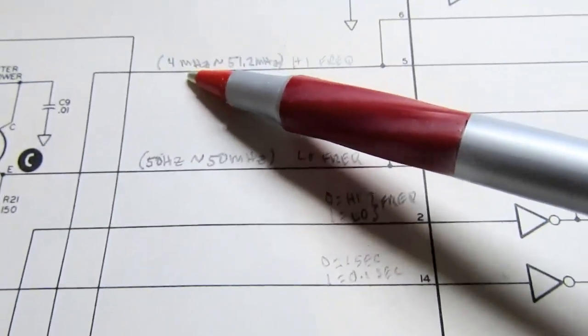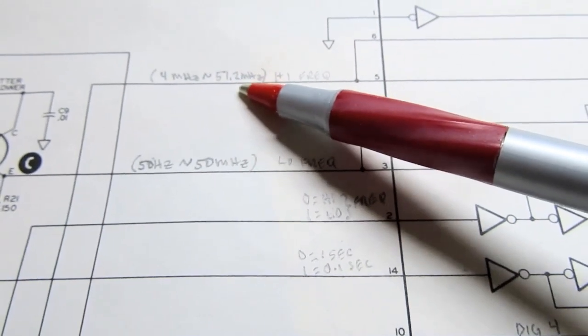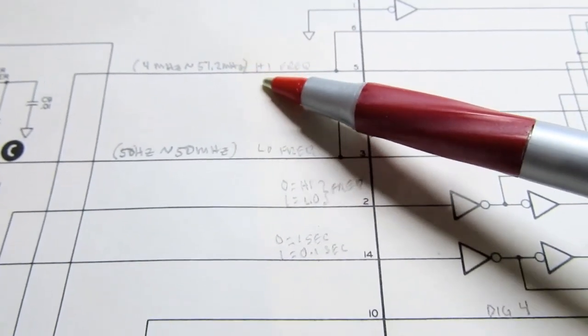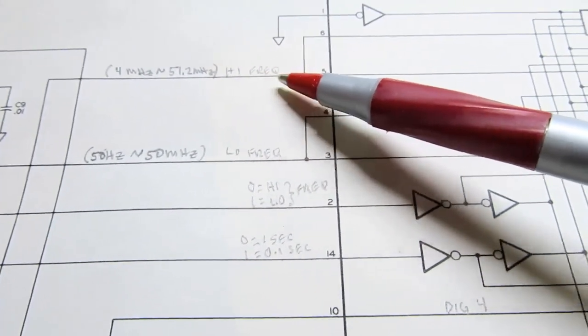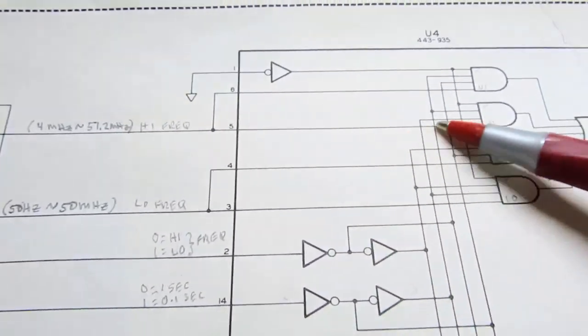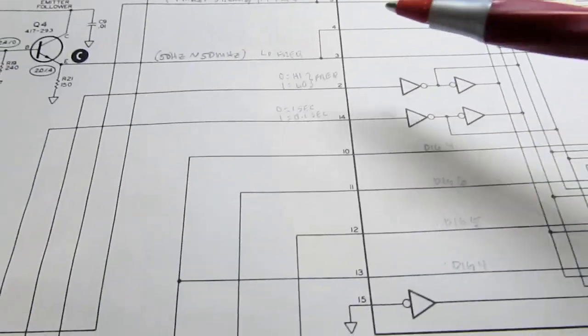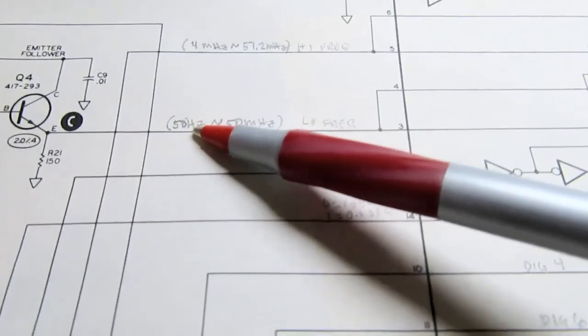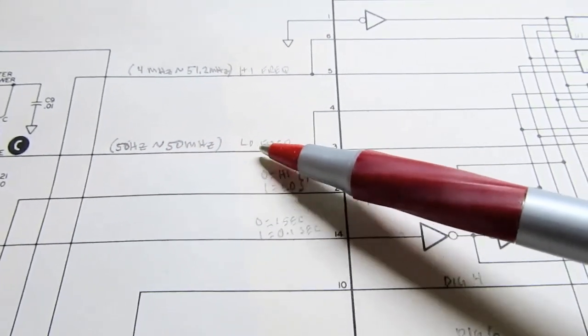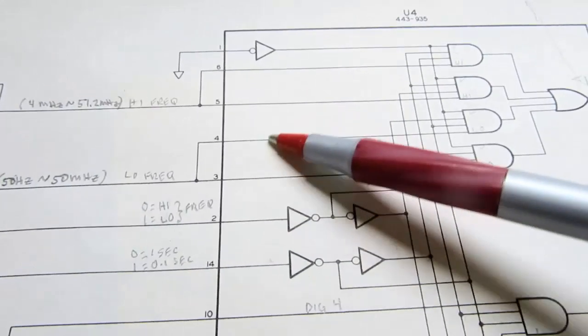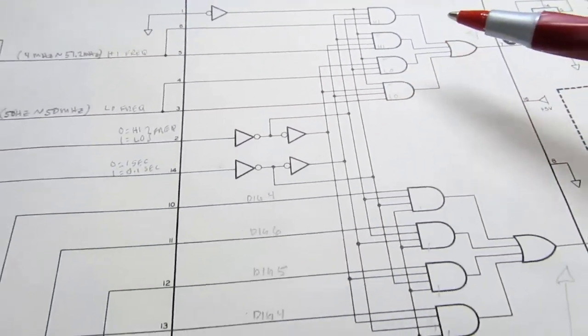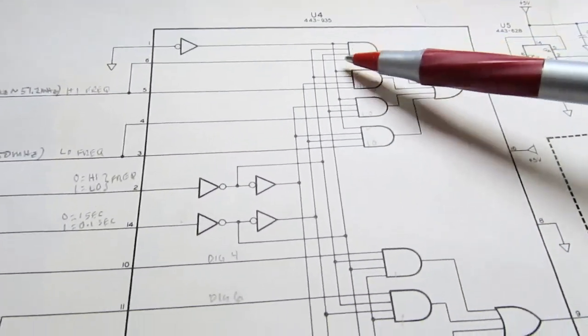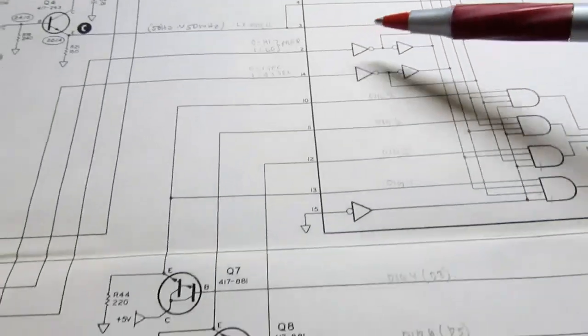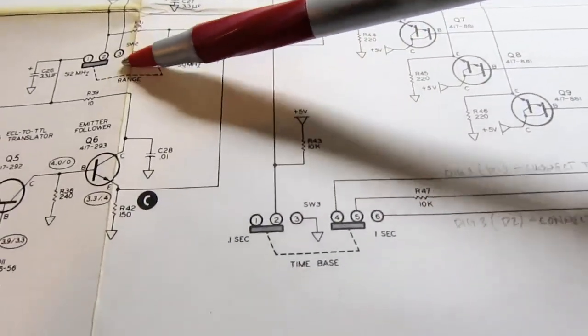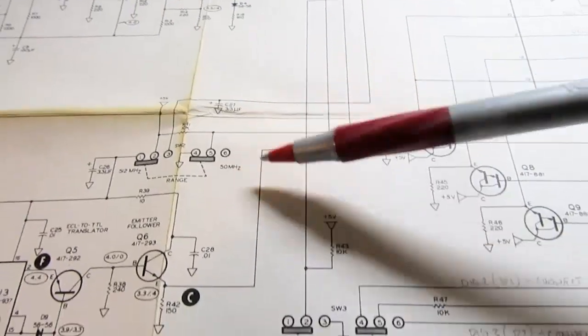So basically what we have here is the scaled down 4 megahertz to 51.2 megahertz signal. That's the high frequency input, and it's applied to 2 of the inputs of the upper multiplexer. The lower one, 50 hertz to 50 megahertz, the lower frequency range, is applied to 2 more inputs of the lower multiplexer. Which of those signals goes through depends on what the range switch and the time-base switch are set to.